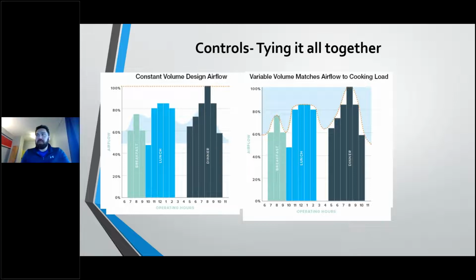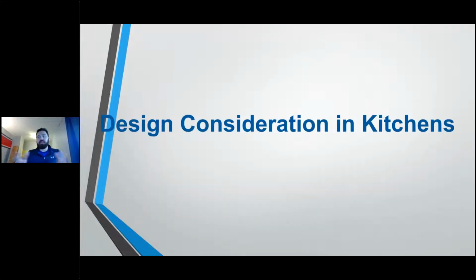So now that we have a base understanding of what goes into a kitchen ventilation system, and I know for a lot of you that was extreme review and you're saying, hey, Mike, I know this. Hopefully it's good information for other folks. But now that we understand the basis of what goes into a kitchen ventilation system, how do we design these systems? So I said to start that in my opinion, designing kitchen ventilation systems is relatively easy. And the reason for that is that code is going to dictate a lot of what your CFM or what your capacities are going to be.